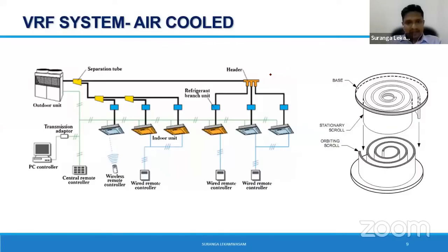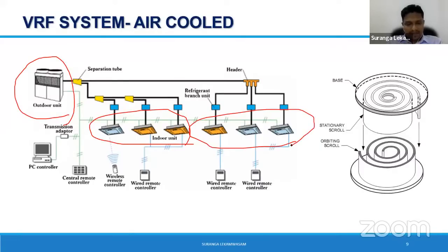Well, on top of that, we have the system called the VRF system. People call it VRV also, but the correct term is VRF, variable refrigerant flow systems. There you can see, again, you have a single condenser unit that can be connected to multiple indoor units. Similar to the previous system, but you can go for bigger capacity in a VRF system compared to the multi-split, right? That is the benefit. So you can see here you have to lay only one set of pipes.